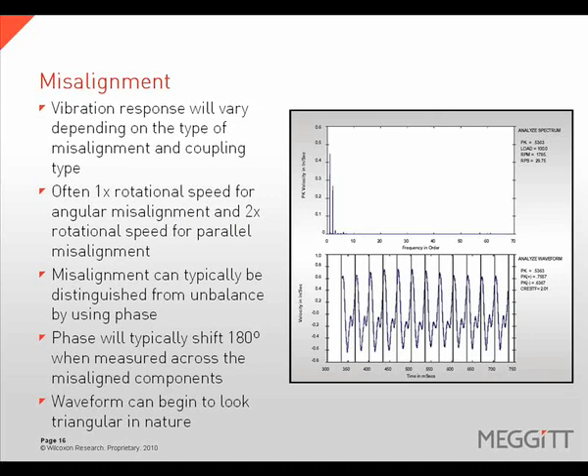The vibration response from misalignment will vary depending on the type of misalignment and the coupling type. Angular misalignment will often have a 1x rotational speed response, while parallel misalignment will have a 2x rotational speed response. Phase measurements will help distinguish misalignment from other faults like unbalance, with phase readings shifting 180 degrees when measured across the misaligned components. The waveform will also begin to look triangular in nature.